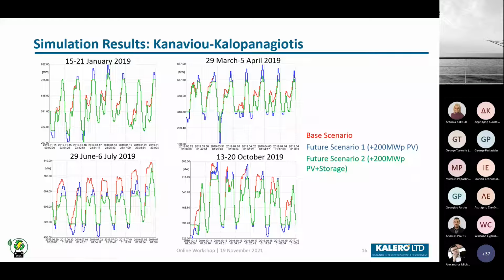The impact of storage - pump hydro storage and, to some degree, the battery - is observed on the green line, providing load peak shaving during high demand periods as well as load leveling during low demand periods. During evening times, energy is extracted from the storage elements into the grid, flattening out the demanded power from the power stations. During low demand periods, when energy is significantly cheaper, energy is extracted from the grid to charge up the storage units.